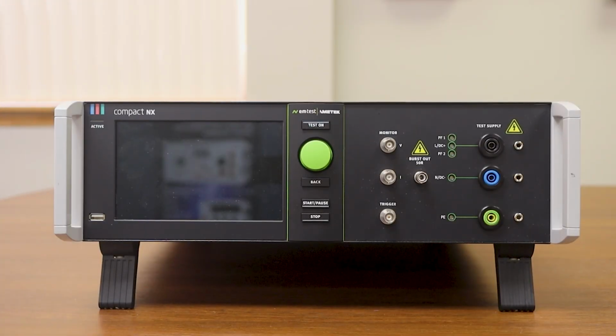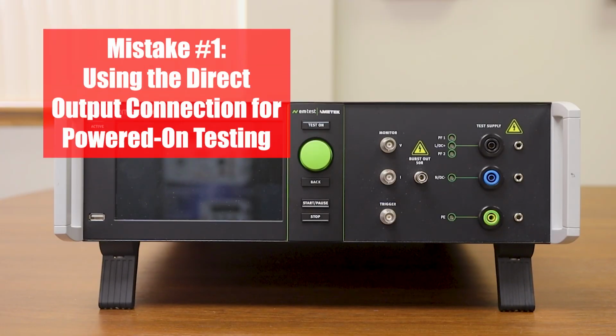First, and oftentimes the most destructive mistake we see with transient generators, is using the direct output connection for powered on testing. This is a big issue. The direct output is used for a few different purposes: power off testing, connections to CDNs. However, all power on testing should be run through the coupling-decoupling network.